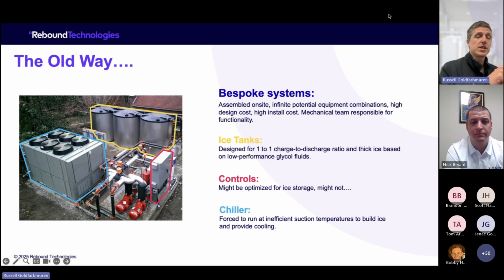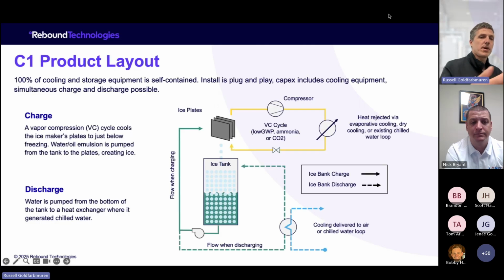And the chiller operation or the compressor operation is a lot more efficient because our compressors are designed to only make ice. We've picked a technology and a compressor that's running right at its optimum, middle of the envelope efficiency. And we're not asking a chiller to run half of the time at a 40-degree suction temperature and half of the time at a 20-degree suction temperature. So all of our refrigeration system is designed explicitly for exactly the case that we're looking at. And so when you look at our product, everything is designed, packaged in this unit.